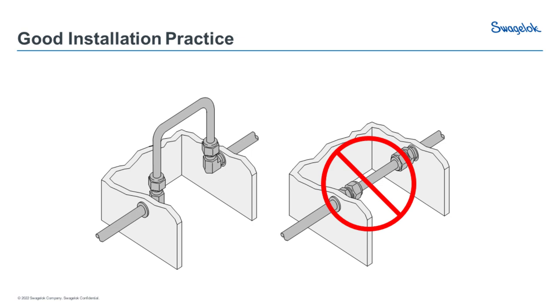This one is an obvious point, but I've seen it — the tube on the right, there's no way you're getting it out unless you remove one of the fittings left or right. The one on the left you've got what I'd call a maintenance loop — you undo the two nuts after depressurizing and isolating the system, and you just lift it out. You've got access to either side that way — nice and simple. It's that thought process and planning pre-installation which can save obviously a bunch of time.